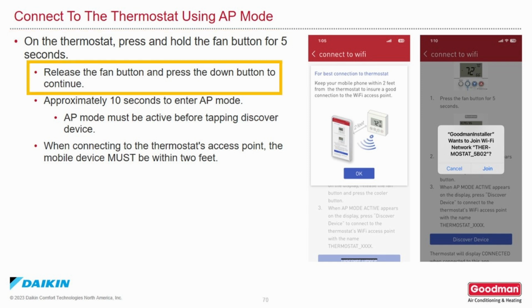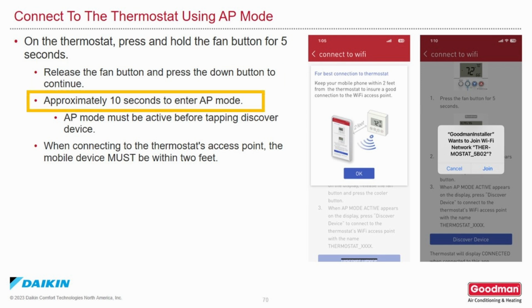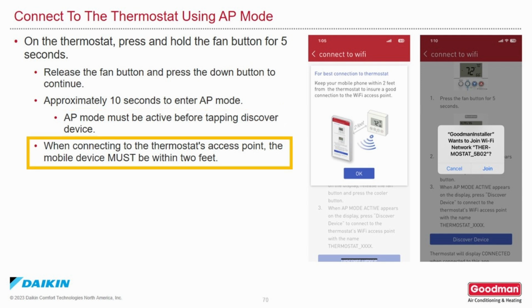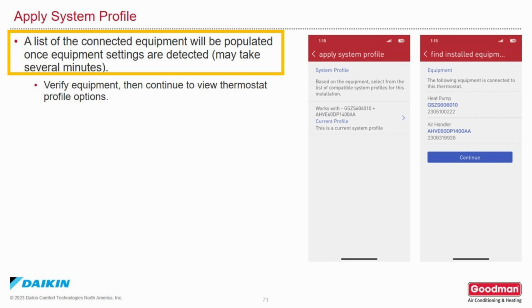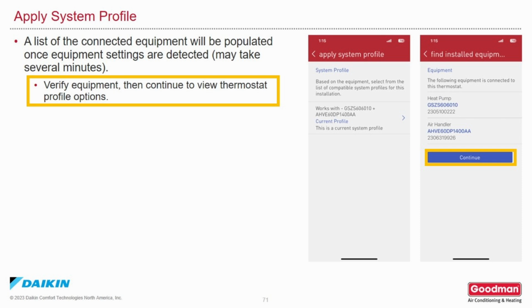Release the fan button and press the down button to continue. It takes approximately 10 seconds to enter AP mode. AP mode must be active before tapping Discover Device, and when you are connecting to the thermostat's access point, the mobile device must be within 2 feet of the thermostat. A list of detected equipment will be populated once the equipment settings are detected. This may take several minutes. Verify equipment, then continue to view the thermostat profile options.